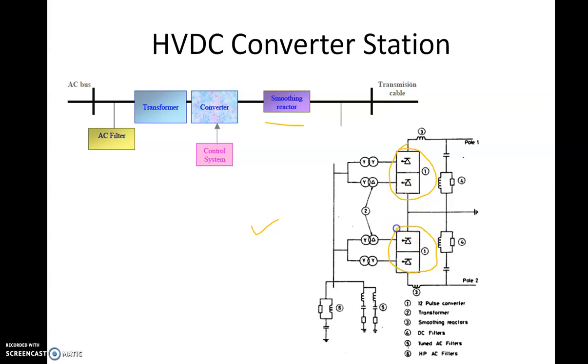These are basically the power electronic switches or converters which convert AC into DC. Then there are transformers — star-delta, with star on one AC side and delta on the other side; it can also be star-star configuration. Why star-star and star-delta? This is to get the 12-pulse operation. Two transformers are used in star-star and star-delta configurations because we need 12-pulse operation.